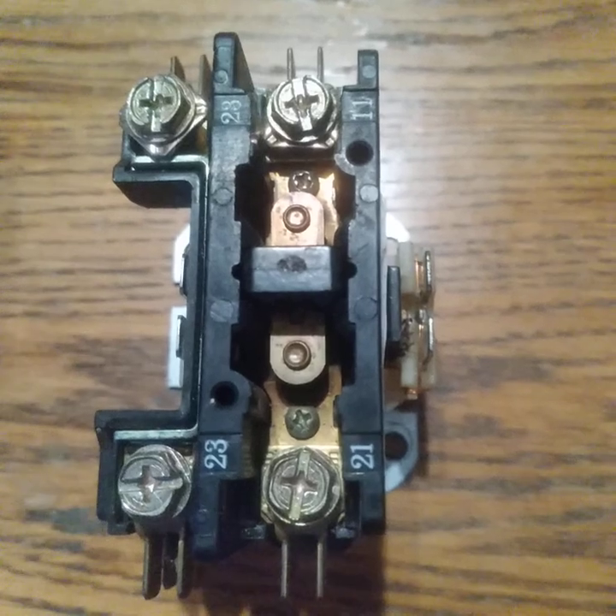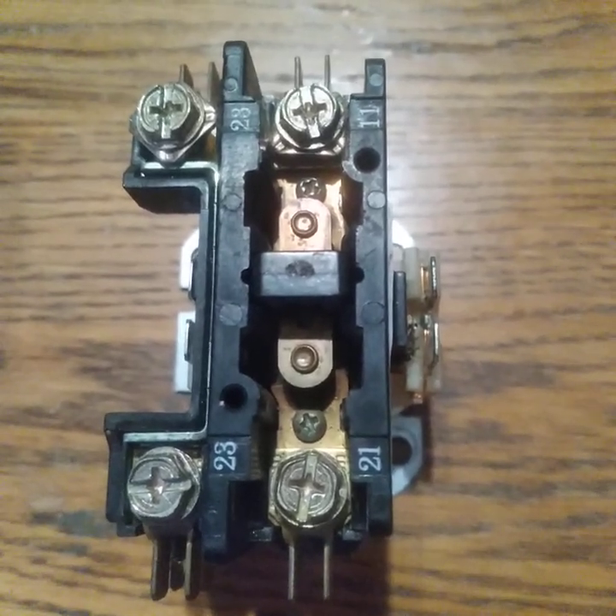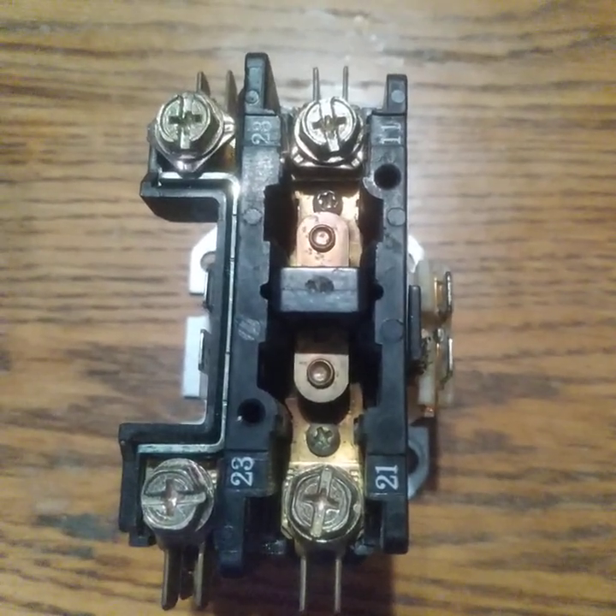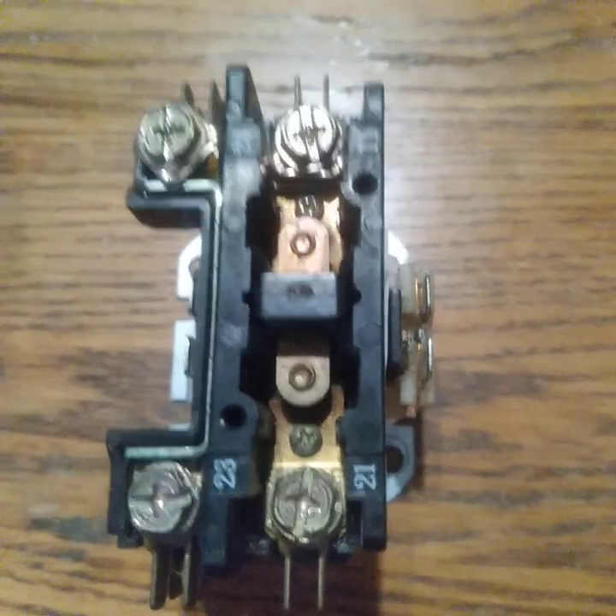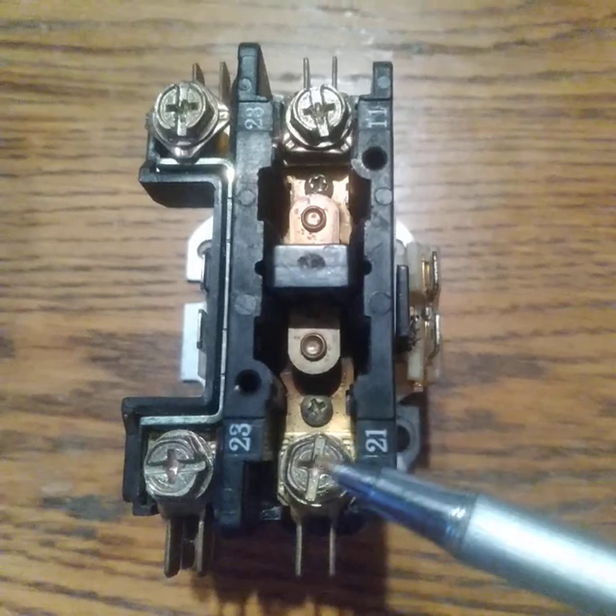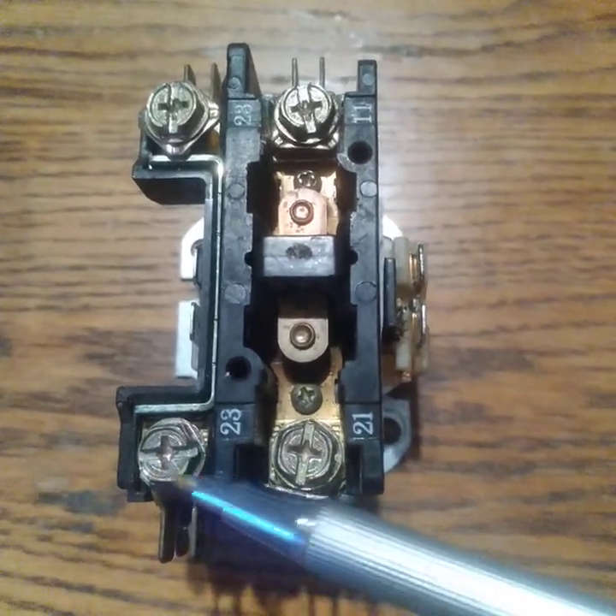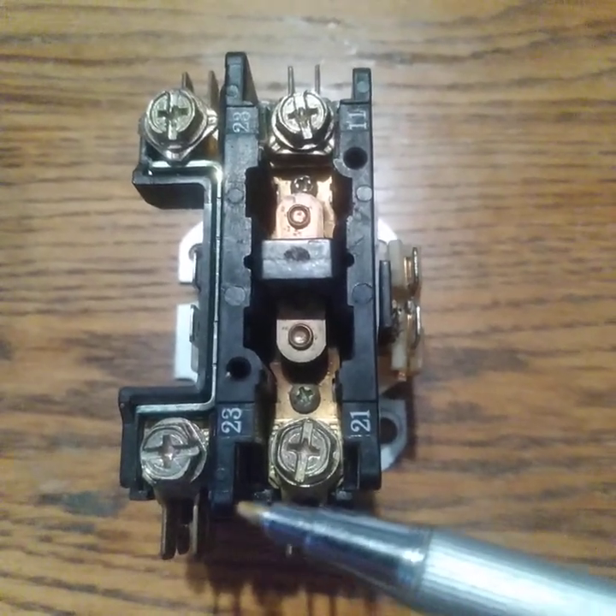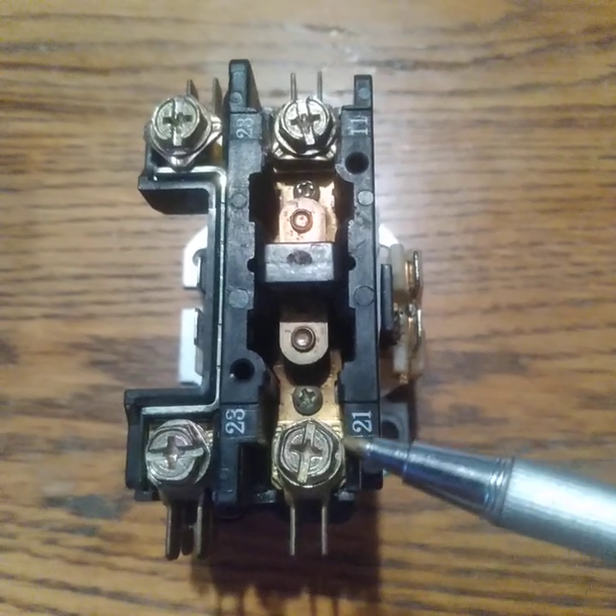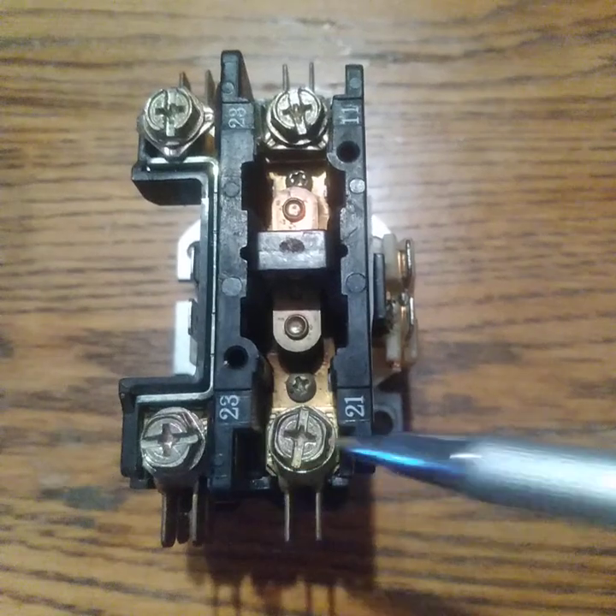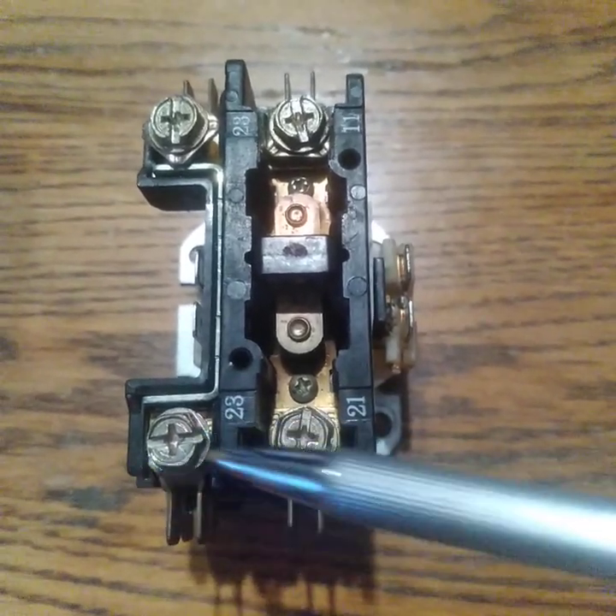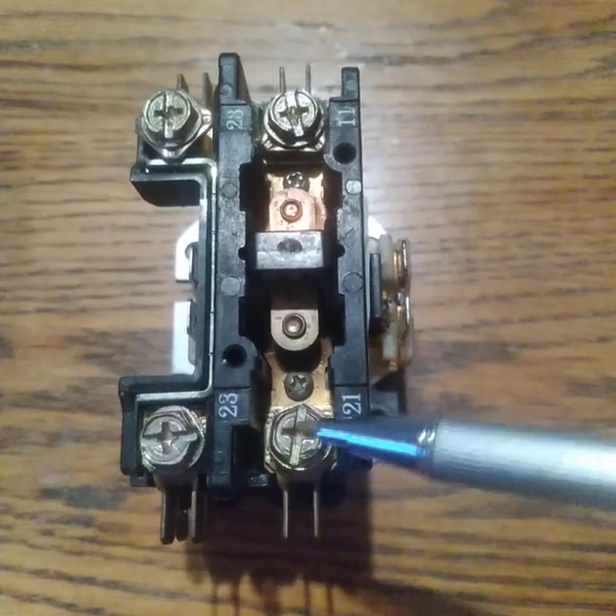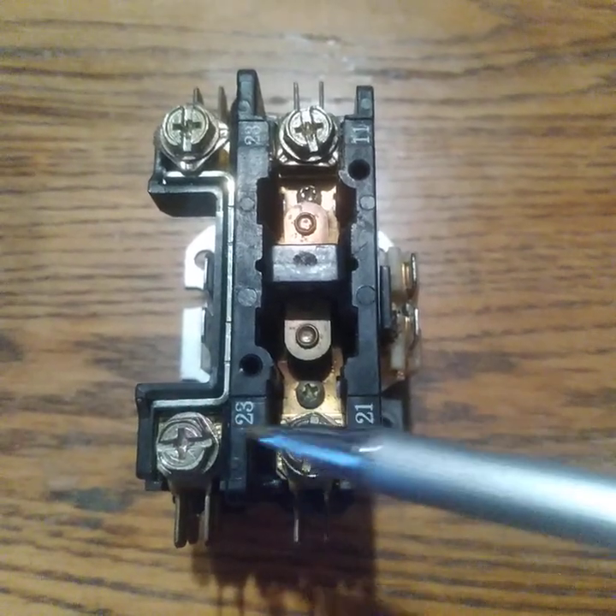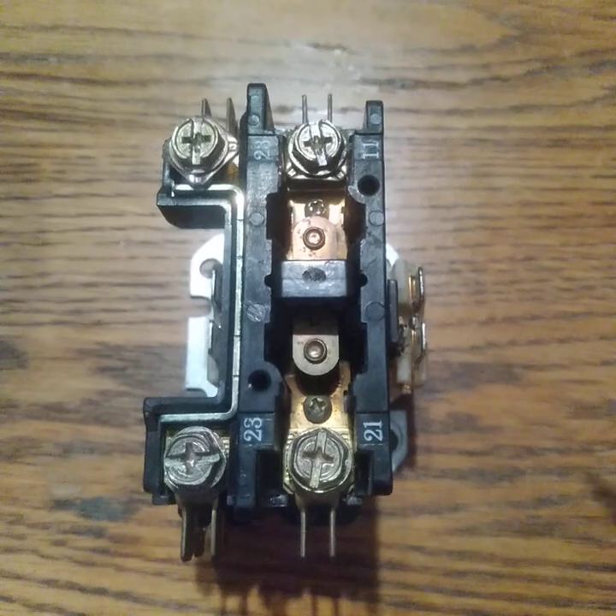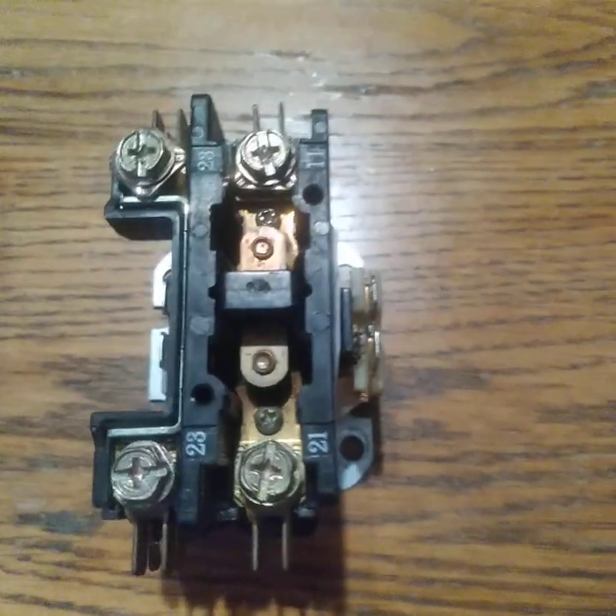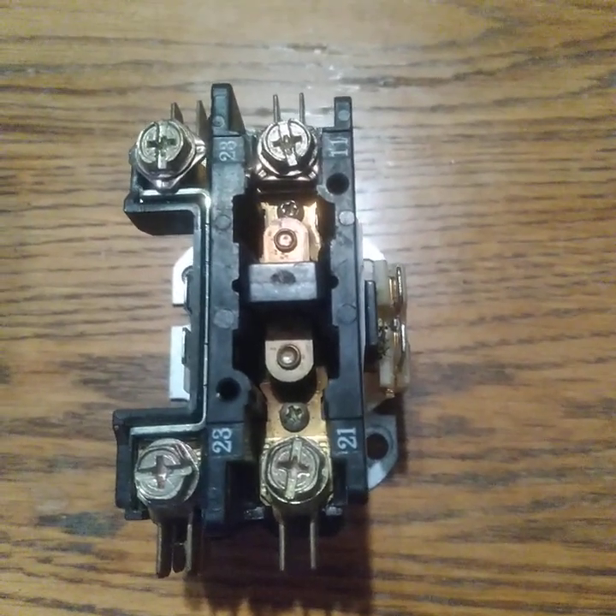When the high voltage feeds in, it feeds in on, say, 240, 220, whatever, and normally on a 30 amp number 10 wire. One leg comes here, one leg comes here. Just for illustrative purposes, we will call this L1, L2. So when L1, L2 comes in, if one puts a voltmeter here to ground, they should pick up about 120 plus or minus. One here to ground, 120 plus or minus, and between the two, somewhere in the range of 240 plus or minus, not exact, but it should bring the high voltage in.